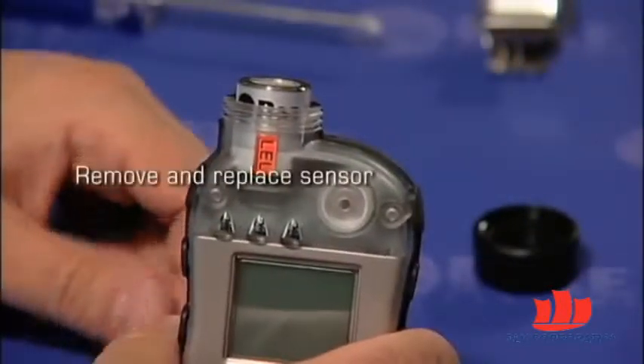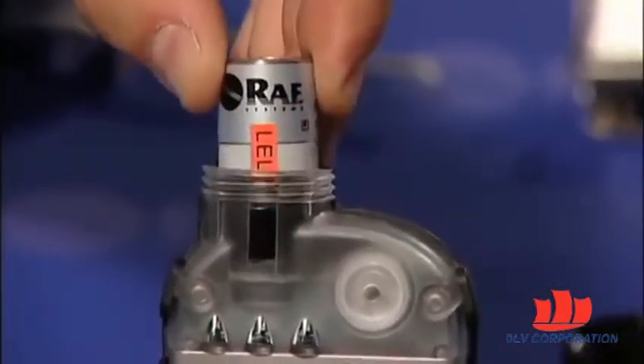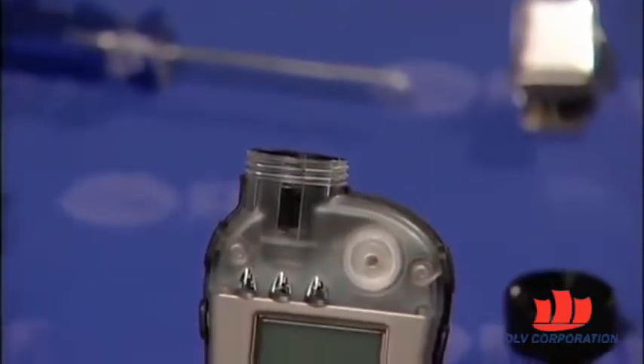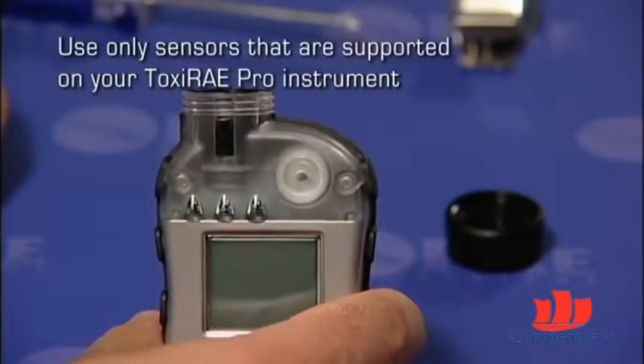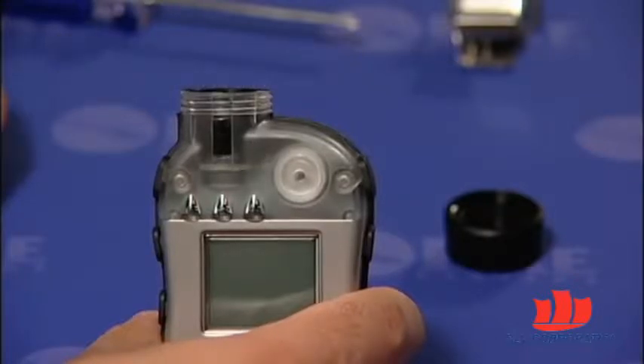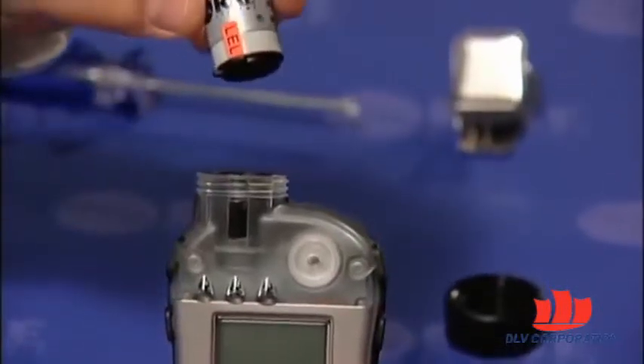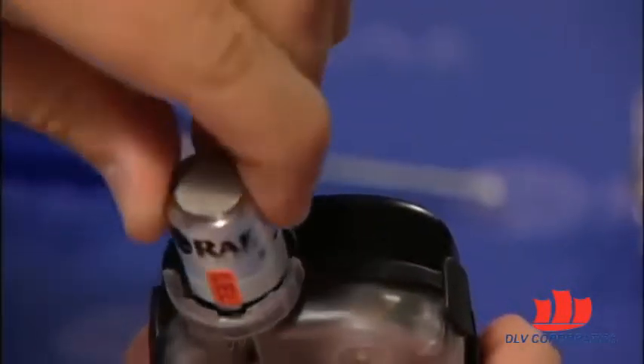Step 3 is the removal and replacement of the sensor itself. To remove the sensor, gently pull it out of its slot with your fingers. The sensors are plug and play, so once you properly reinstall them, the instrument will immediately and automatically recognize them. Make sure that you replace the sensor with one that is supported by your particular instrument. For example, the ToxiRAE Pro LEL would only support the catalytic bead LEL sensor, manufactured by RAE Systems.